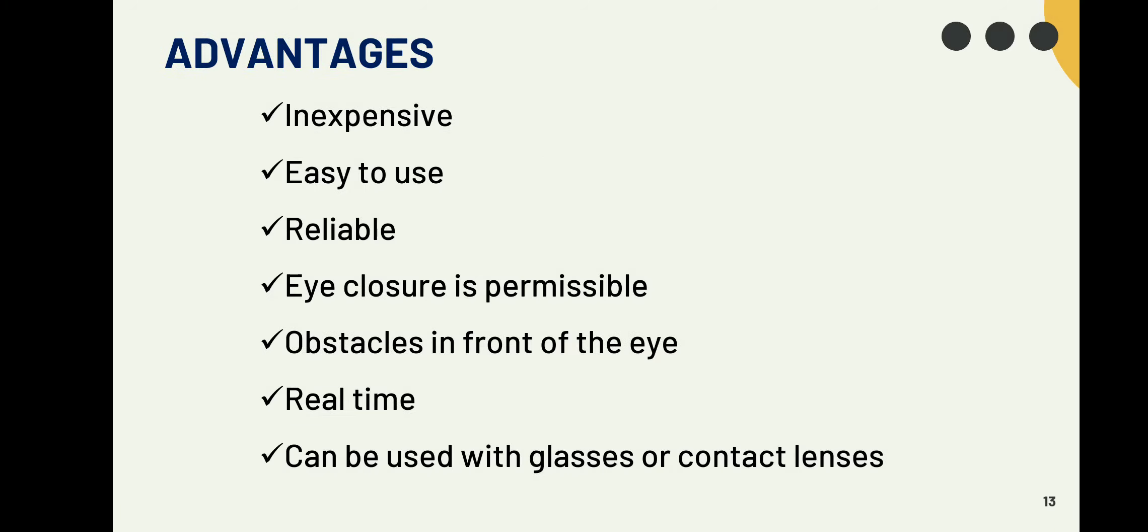Next is advantages. It is inexpensive by cost and easy to use. How is it easy to use? Just place the electrodes on the skin and we are going to acquire the waveform to measure the test. Eye closure is permissible, that is not a disturbance. It can be used with glasses and contact lenses.